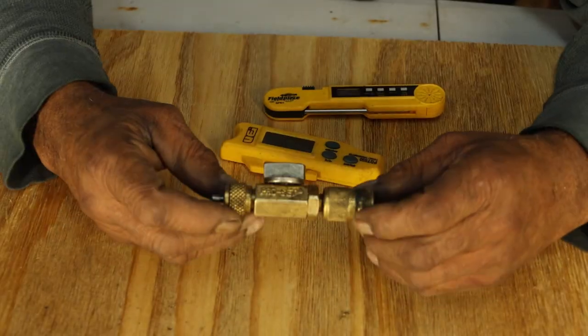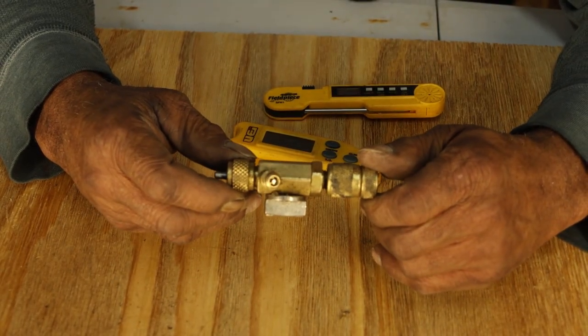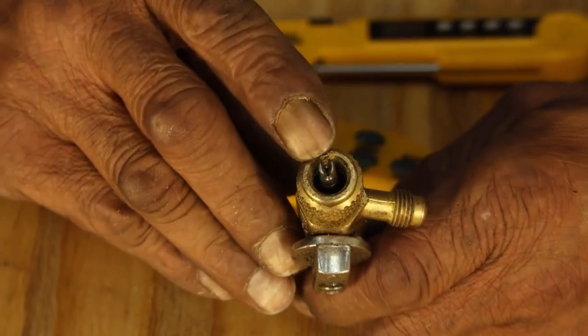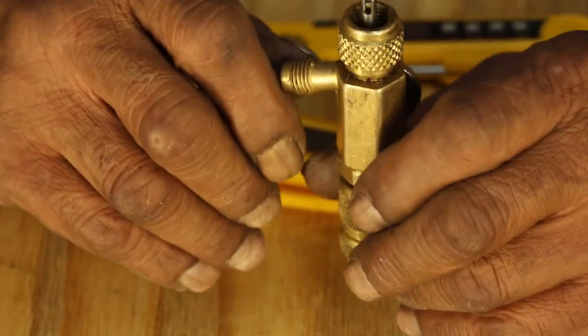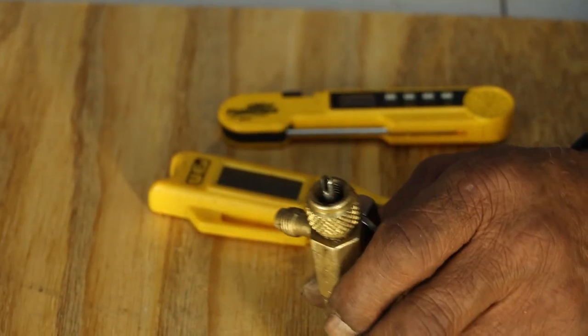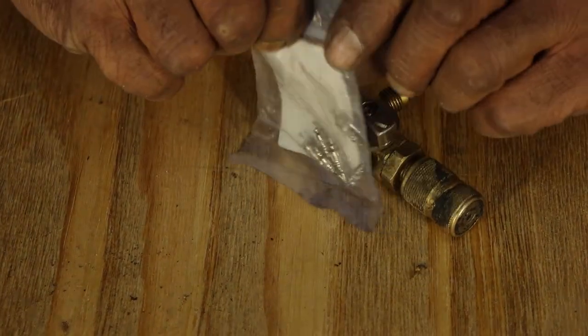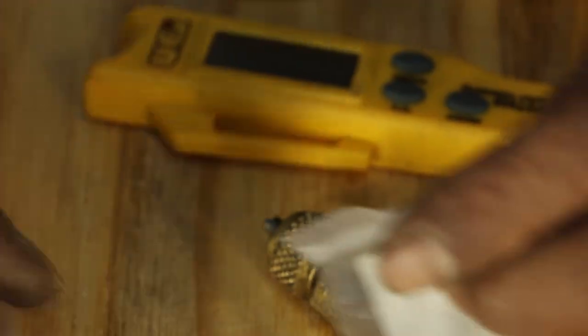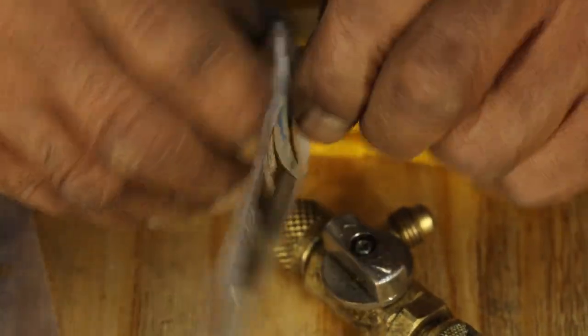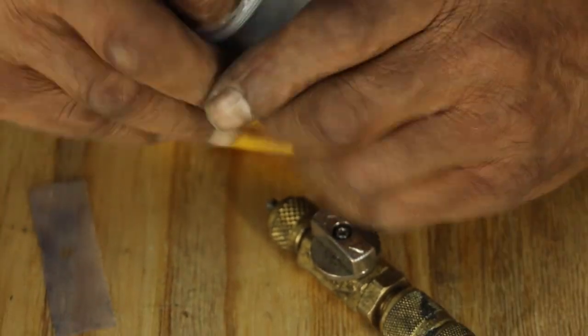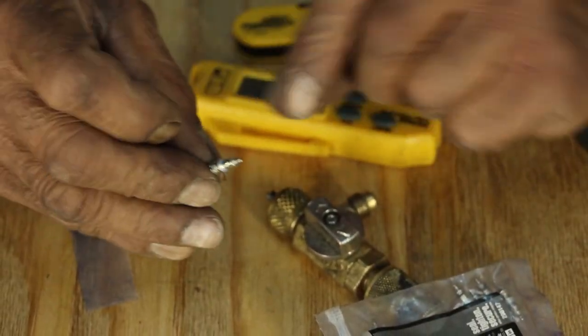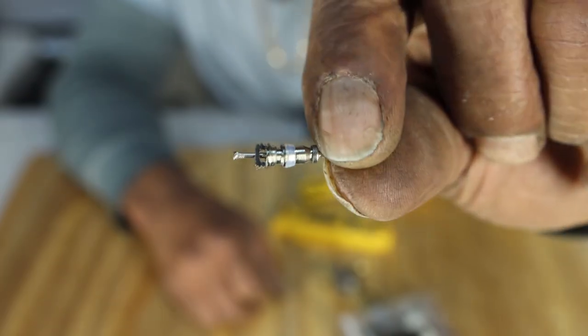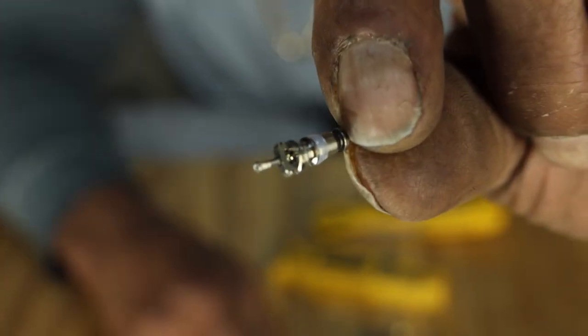All right. This right here is also a service tool. It allows me with this to remove Schrader valves. Give me one moment. Let me show you. This is a Schrader valve. It's the same device that's in your tires on your car. And when you put air in your tire in your car, the pump depresses the Schrader valve and lets the air go in. And once the air goes in, the Schrader valve closes so that the air can't get out.